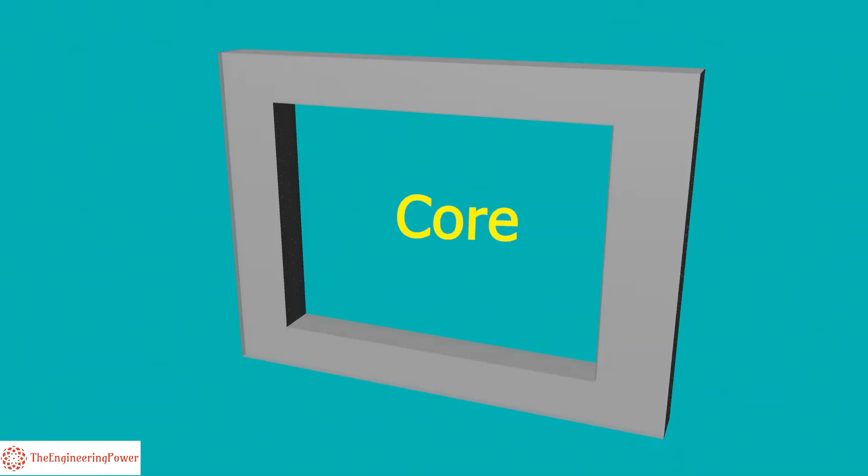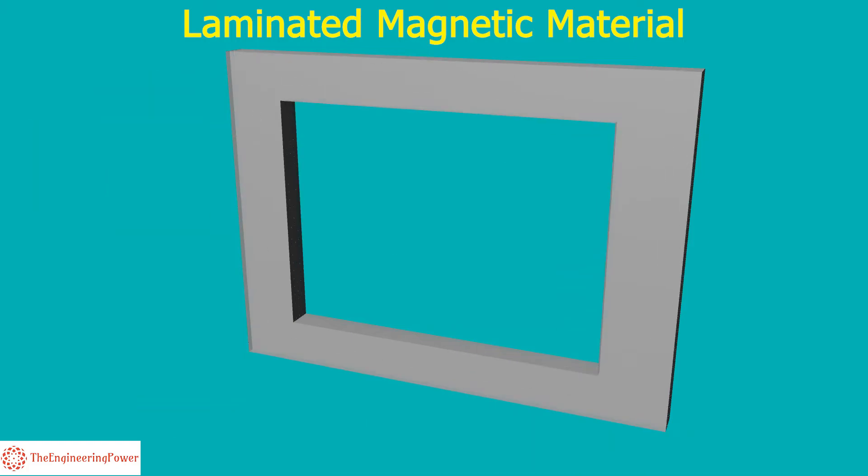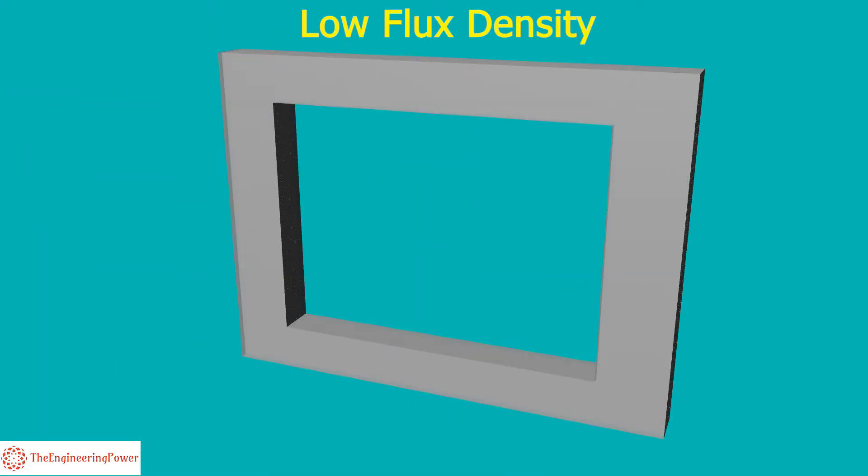Core is an important part of a PT. The core is built up of sheets of laminated magnetic material such as iron or steel operating at low flux density so that magnetizing current is small.